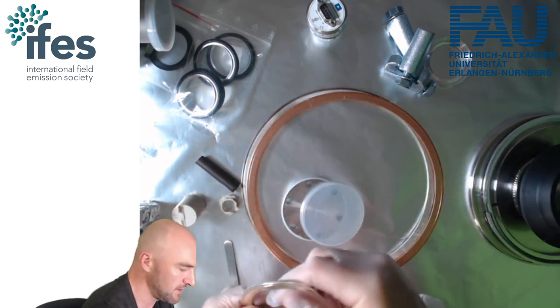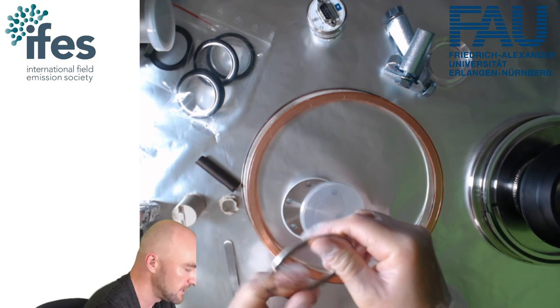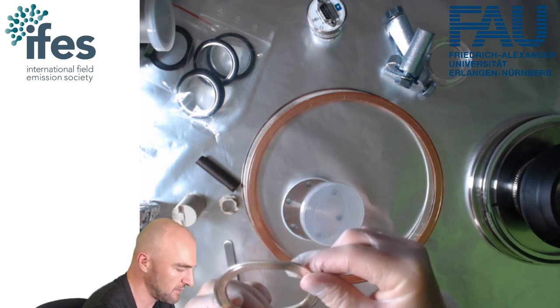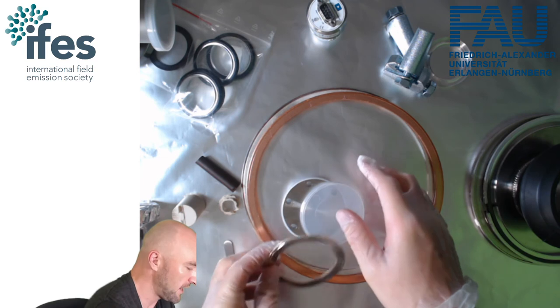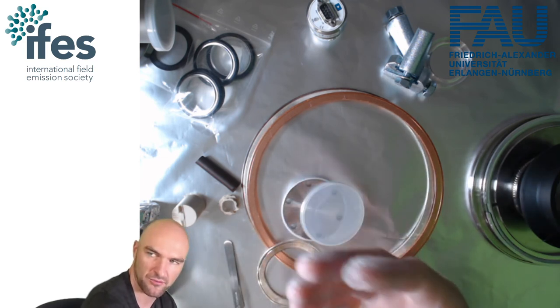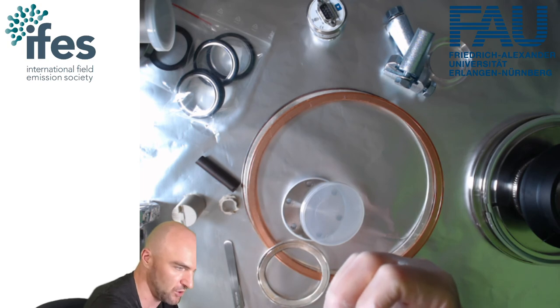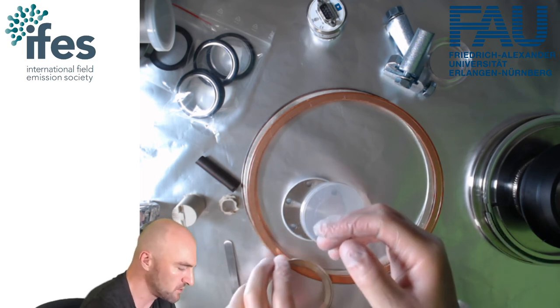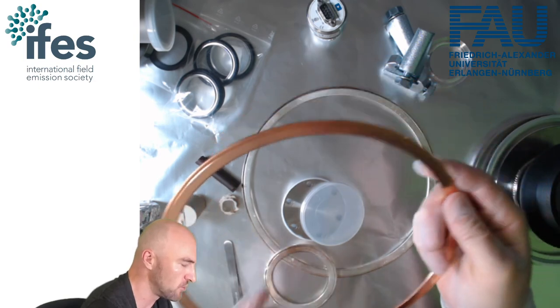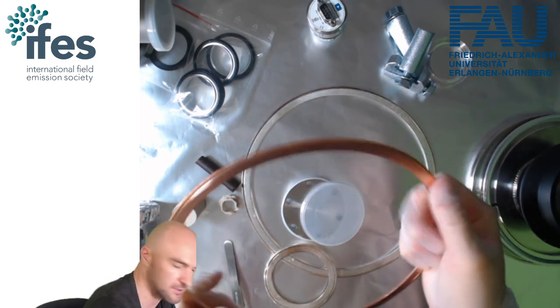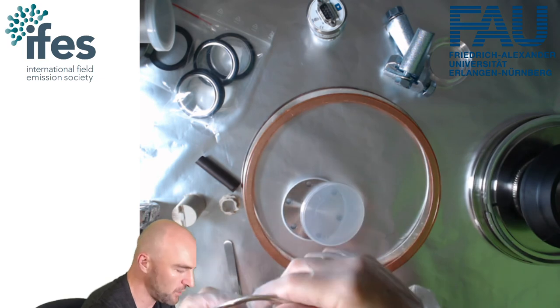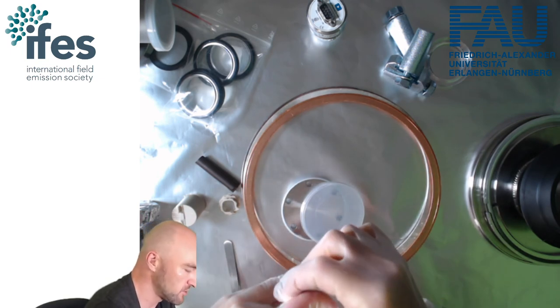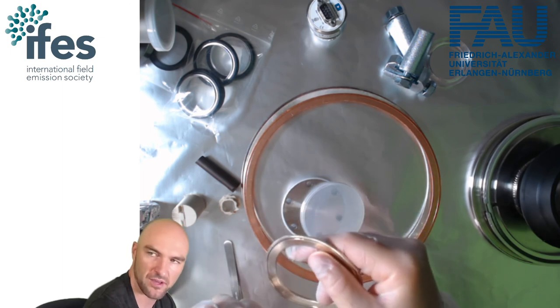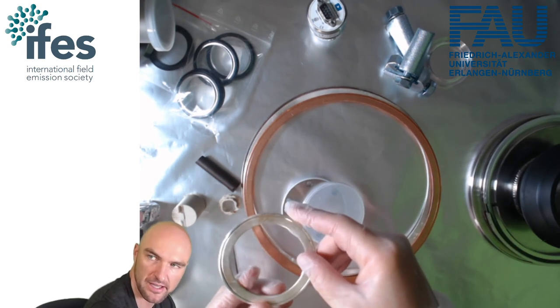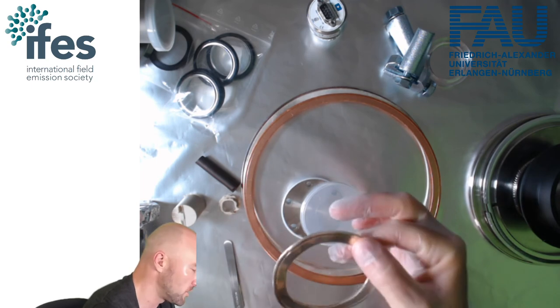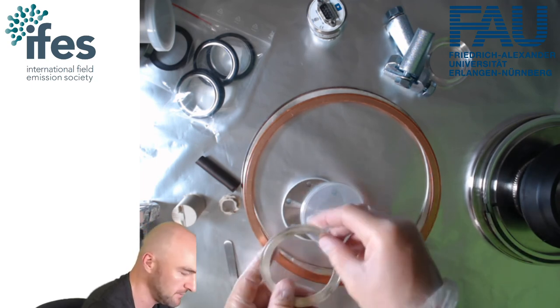The other factor is having the gaskets annealed or not annealed. The difference is mainly that if you have anything where you put a load on, right? So for example, we very often have our load locks bolted on and just freestanding. Then you would want to use something with a little bit of strength. So just a rolled one, yeah, that hasn't been annealed. If you have parts where you cannot have any residual stresses in the part, for example, if you have a viewport, then you want to use an annealed soft gasket so that you don't put stress on the viewport, which might crack the viewport. Okay.